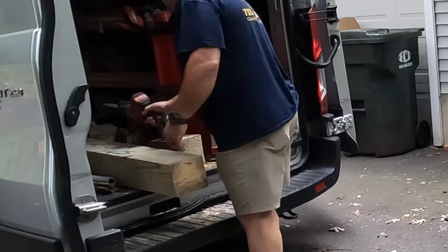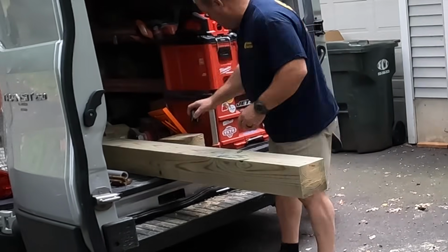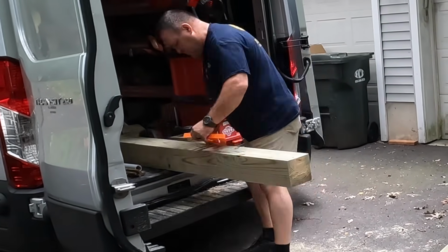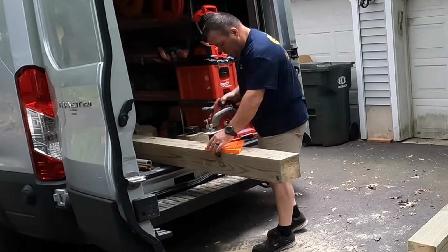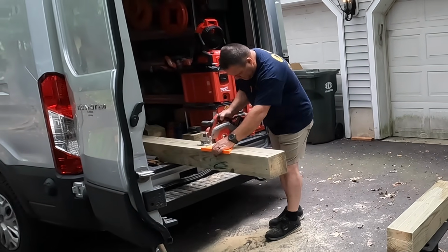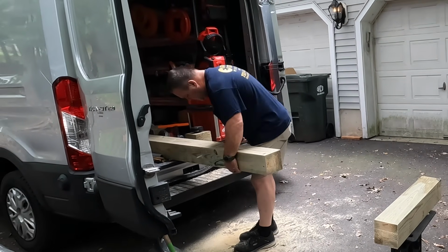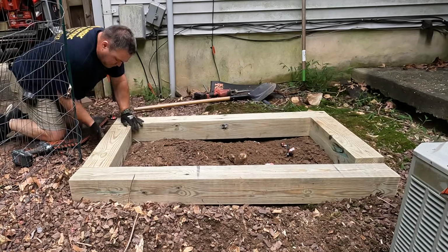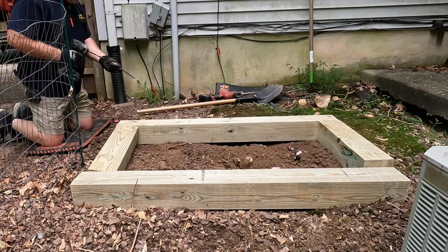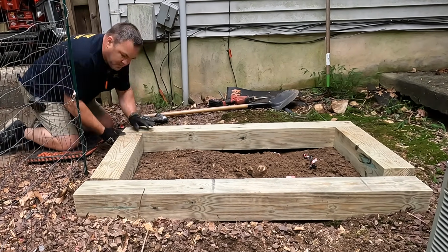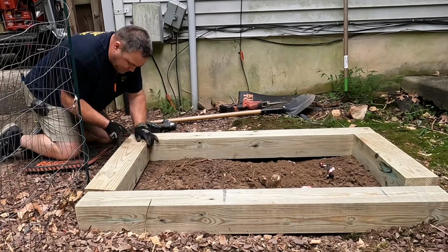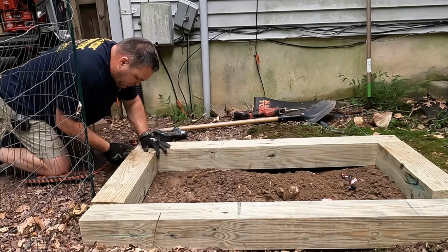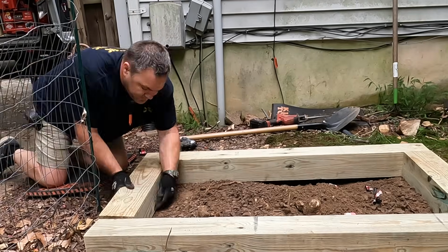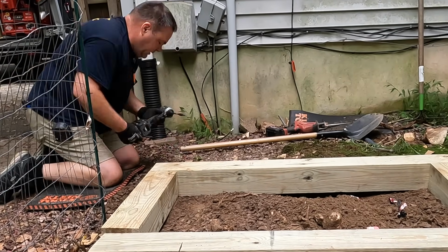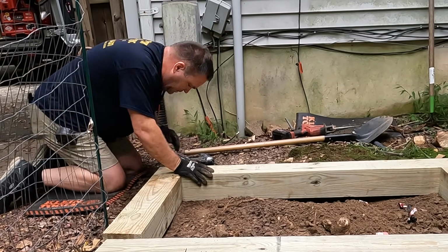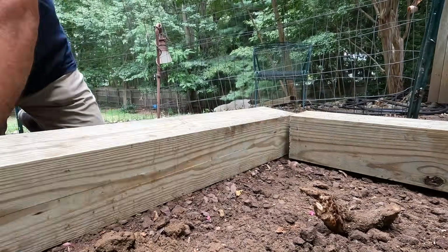The pea gravel you'll see in a moment, we backfill in the center of this frame, and that's to counteract the vibration of the generator. So we make this cutout just a little bit longer than 48 inches. I think this was maybe 52 inches from side to side, and then back and forth you got to have a minimum of 24, and that was somewhere around 26 inches. So make sure you make the right cuts, and then we assembled this with some 10-inch lag screws, landscape lag screws, to get that going just right.